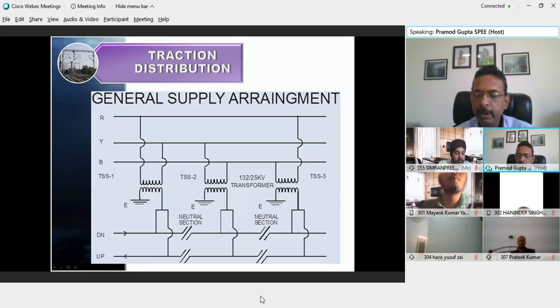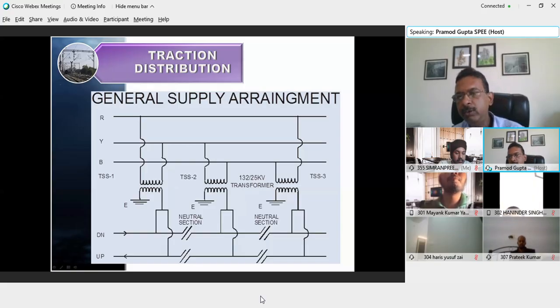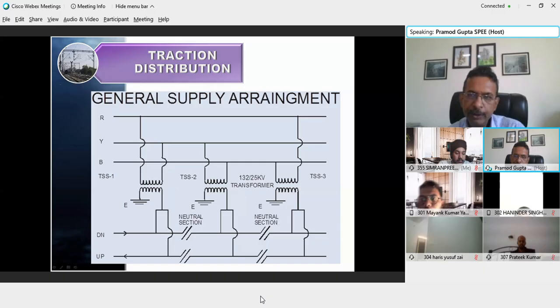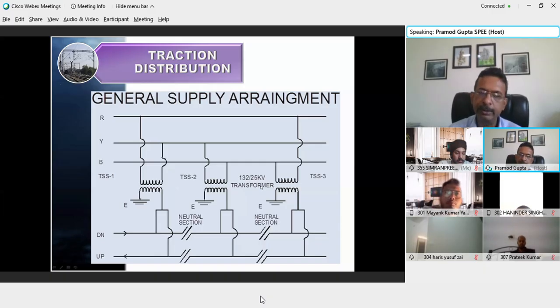When I want to do this, we have a bridging mechanism, or bridging interrupter, provided at the neutral section. When we operate that bridging interrupter, the power supply from TSS1 gets extended to the power feeding zone of TSS2. That is another function performed at the location where we have the neutral section.